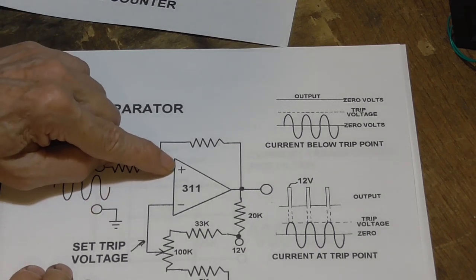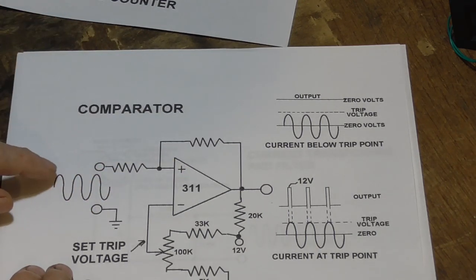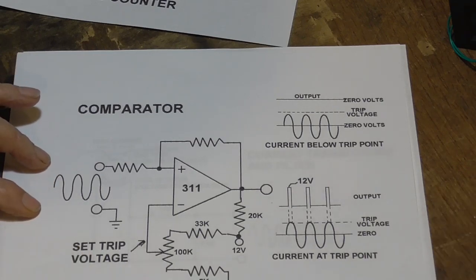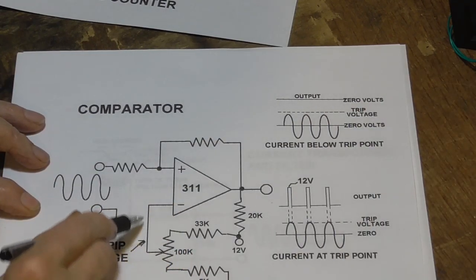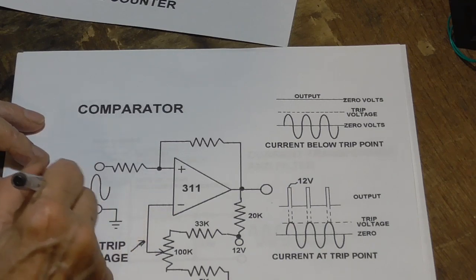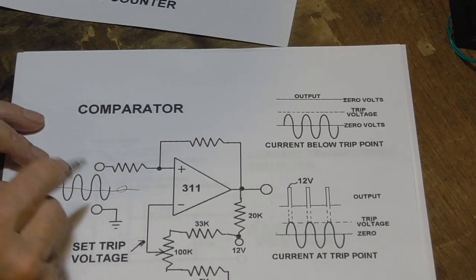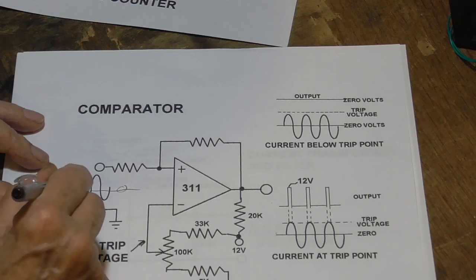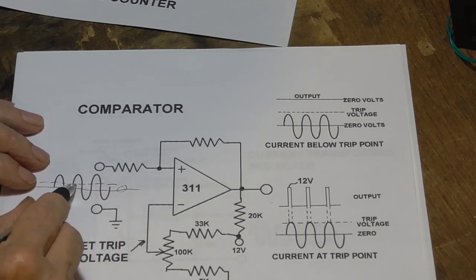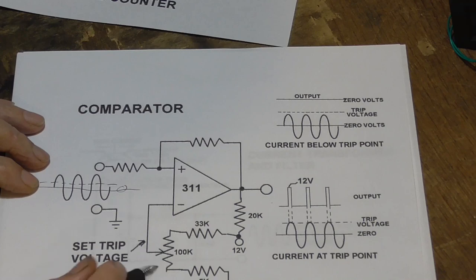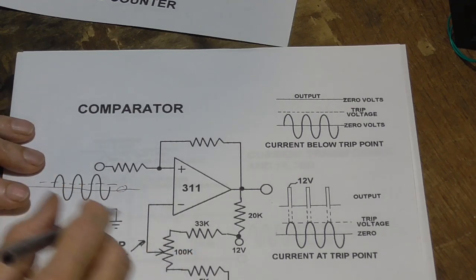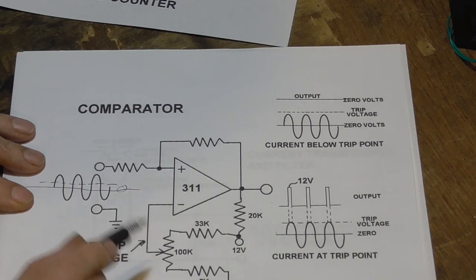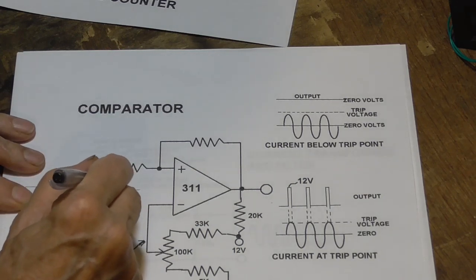We're going to hook it up so that it's non-inverting. So when we have a certain amount of voltage set on our input, we're going to have 0 volts here, and our input level will be set at some voltage set by our trip voltage potentiometer, which will be on the front panel. And we'll have that calibrated in amps. So let's say that 1 amp is 1 volt. We'll have this set at 1 volt.